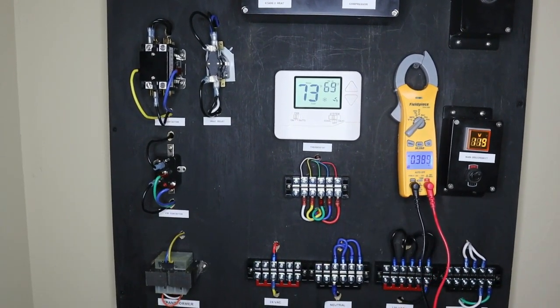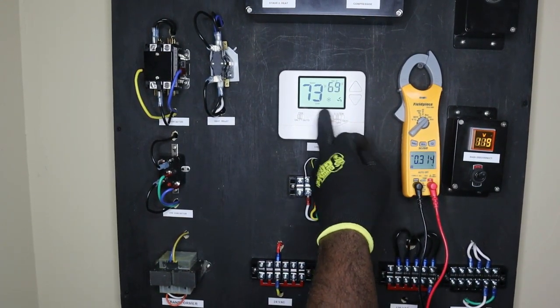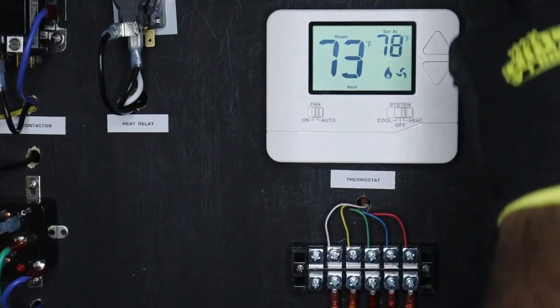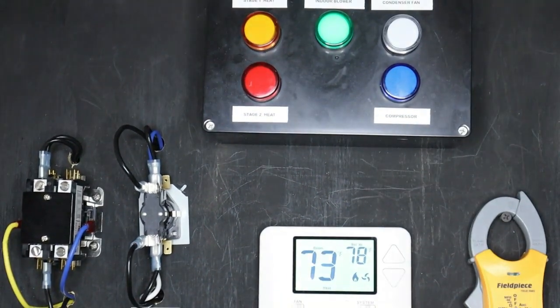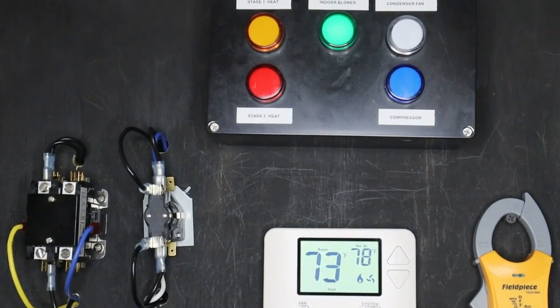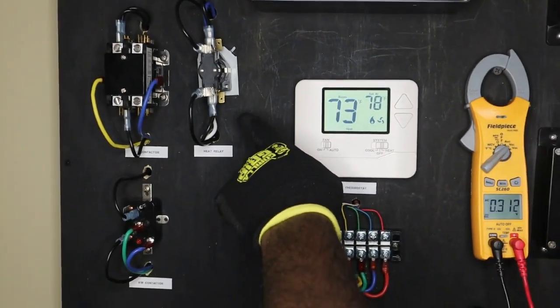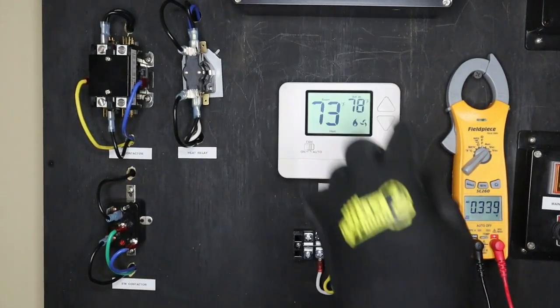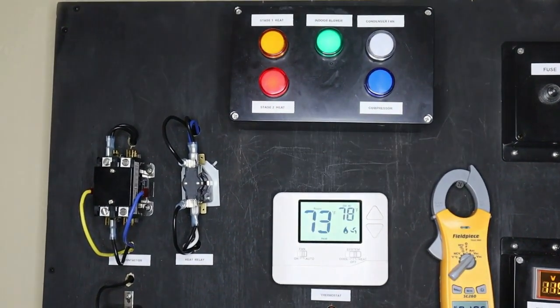For the last test let's test how our heat relay works. Now let's say we're calling, this is on auto, we're calling for heat. Now as you can see the moment we call for heat our compressor and our condenser fan shuts off. Now this heat relay has an on-delay timer. So as you see it took a few seconds to turn on. As you can see we have our stage 2 and stage 1 heat LEDs now lit.